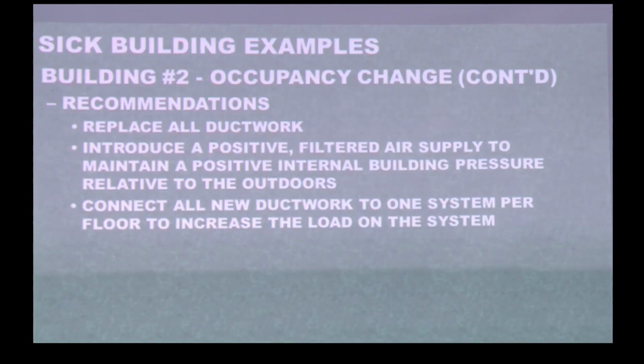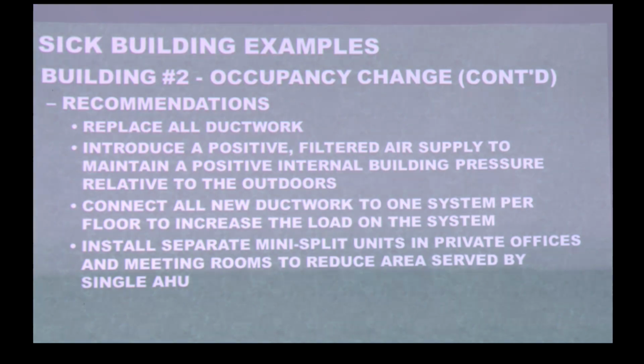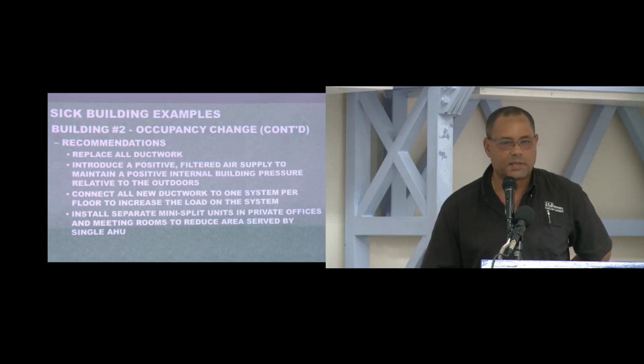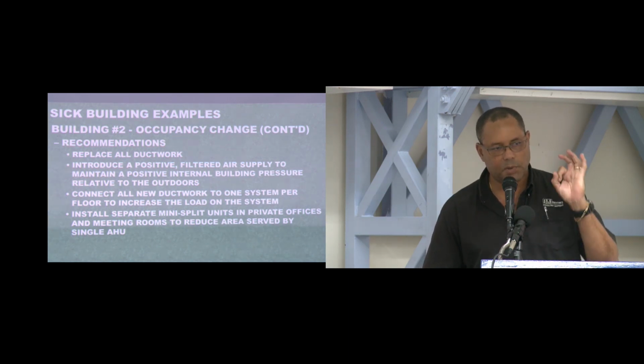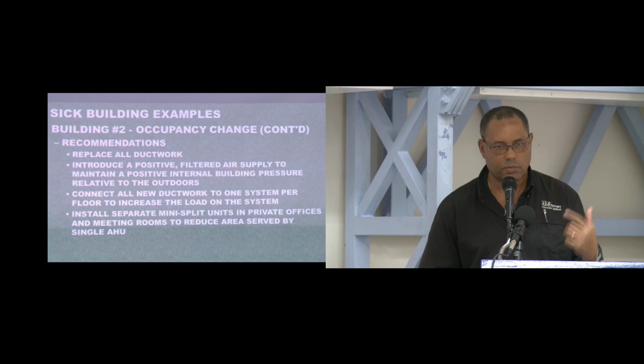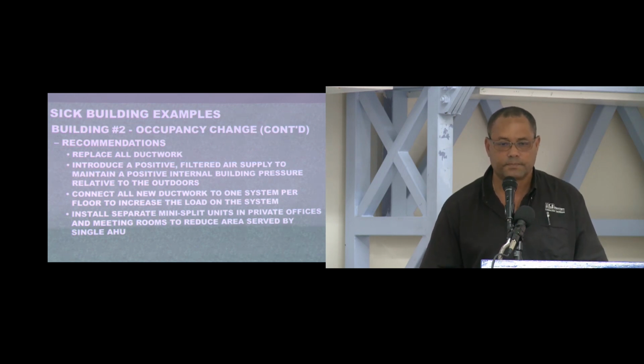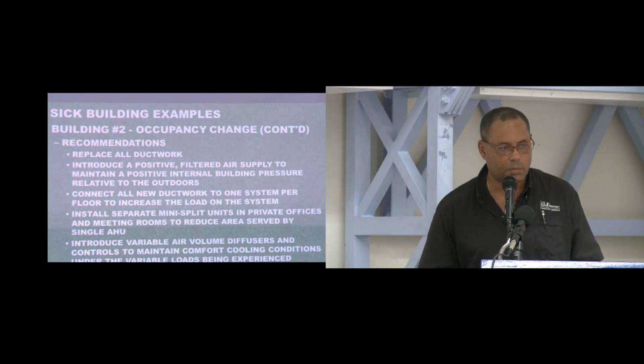Introduce positive filtered outdoor air to the space. Make sure that you are controlling the volume of air and the condition of the air that goes into the space. We had 2 air handling units per floor. So what we recommended was that we have one system dealing with part of the floor and install separate split systems in the perimeter offices. What we also did there is connect a small supply from the central system into each office to make sure that they were getting air circulating through those offices that had individual split systems. It worked. No more issues with mold, no more issues with indoor air quality or people getting sick.